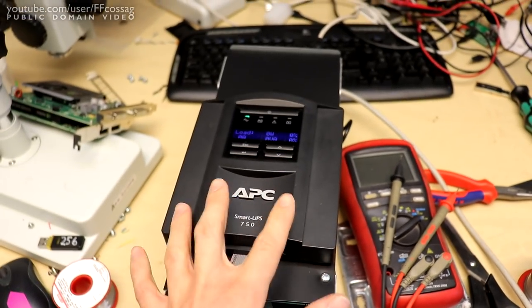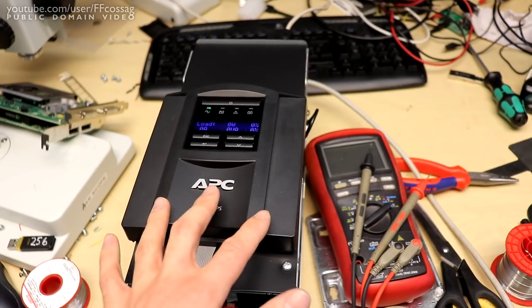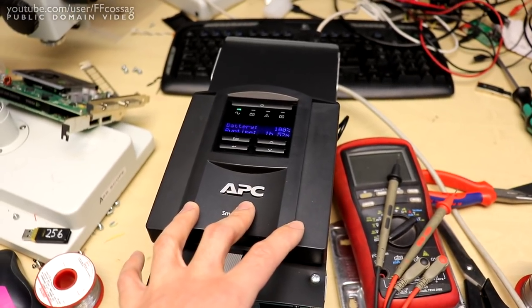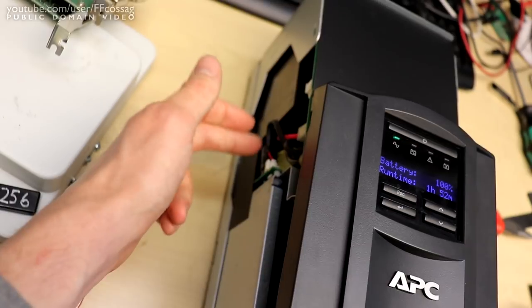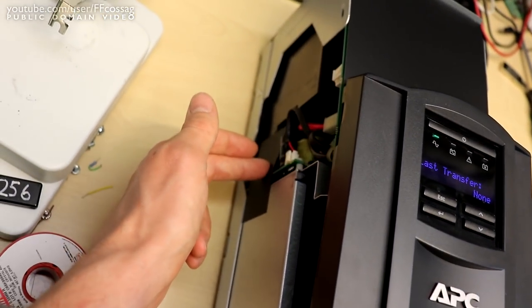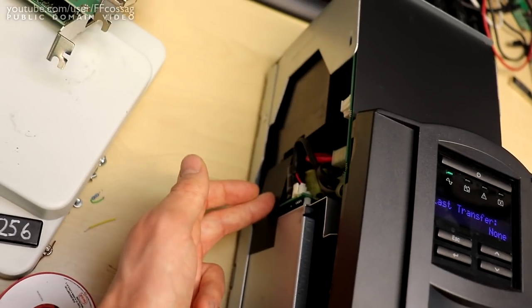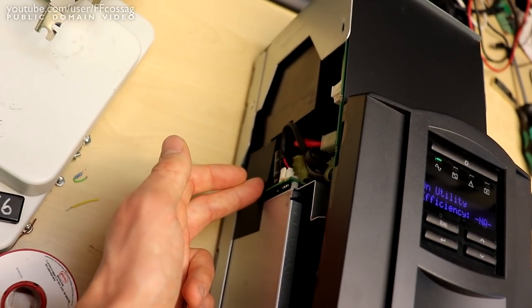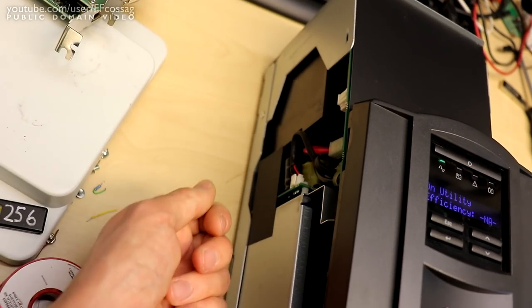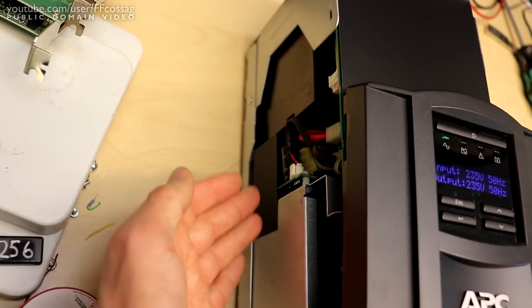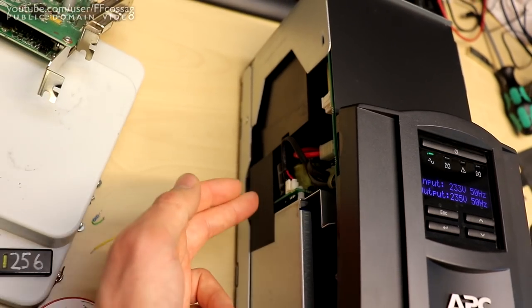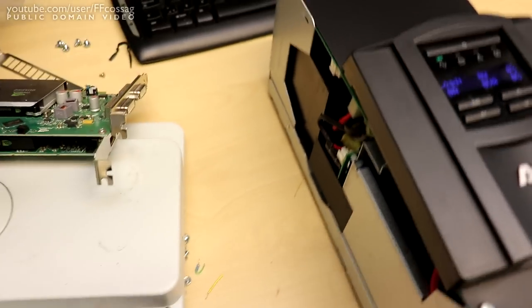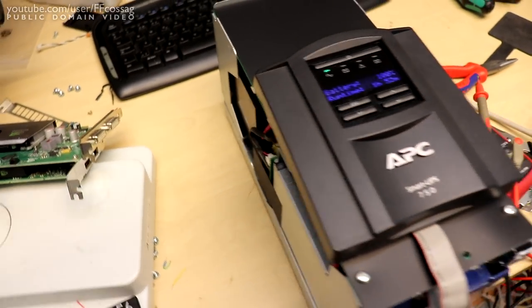When the two bad caps in here go bad, this thing is going to go unstable, kind of crash, not run properly, randomly turn off, issues like that. No battery charging would point towards something gone wrong on that board there. This has a TNY switch chip for the battery charger. These are notorious for failing with bad mains. If you connect the power a lot, if you have lots of transients and stuff, TNY switch chips often go bang.